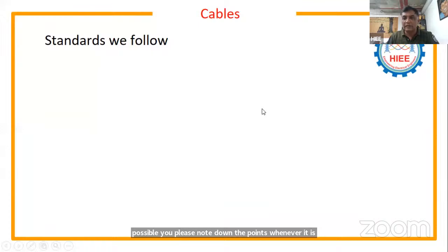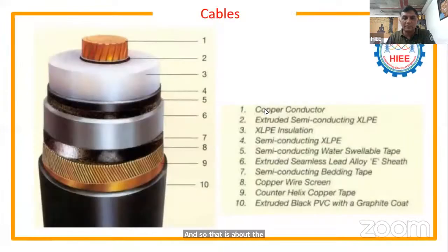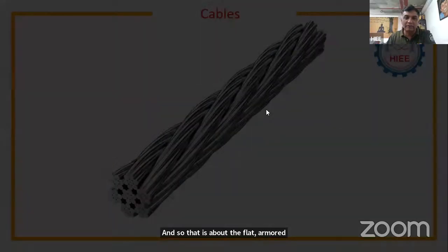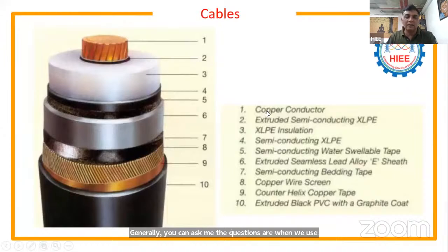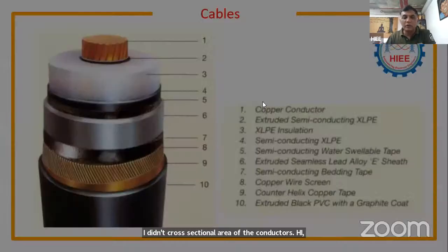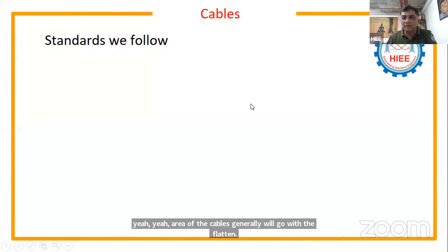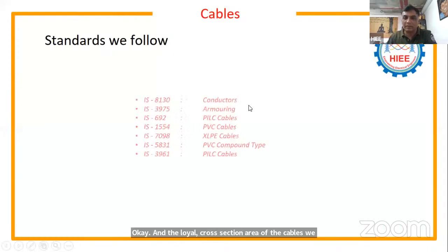So that is about flat armored and wire armor. Generally, you can ask me the question: when do we use flat armor and when do we use wire armor? For higher cross-sectional area of the conductors, higher cross-sectional area of the cables, generally we go with the flat armor. And for lower cross-sectional area of the cables, we prefer to go with the wire armored cables.